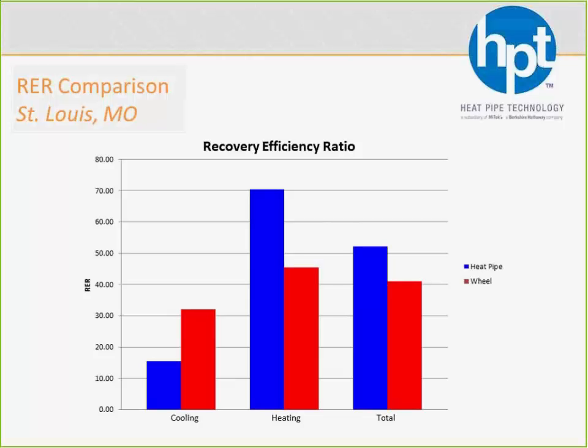But when you look at the heating season, where there's a lot more delta T's to go get anyway, but we're not hurt by the fact we're not recovering latent heat, you actually find that we're a more efficient recovery device because we're just adding static pressure, and not as much as a wheel. So even when you add up the whole year for a place like St. Louis, you find that we're still, over the whole year, the more efficient energy recovery device.